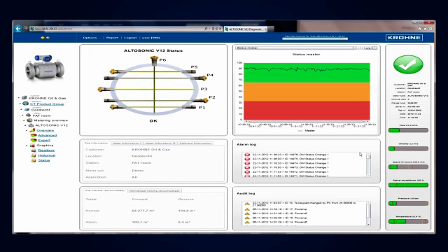And in the expert screen you see the lowest level of evaluations we do. All individual checks that we do are shown here and are given a value. You see, for example, here on velocity there is some warnings and an error on the flow profile velocity. That does not mean the overall health of the meter is not good, but it means on the lowest level we see some warnings. We combine those into the advanced screen and from there we come to an overall health of the meter.